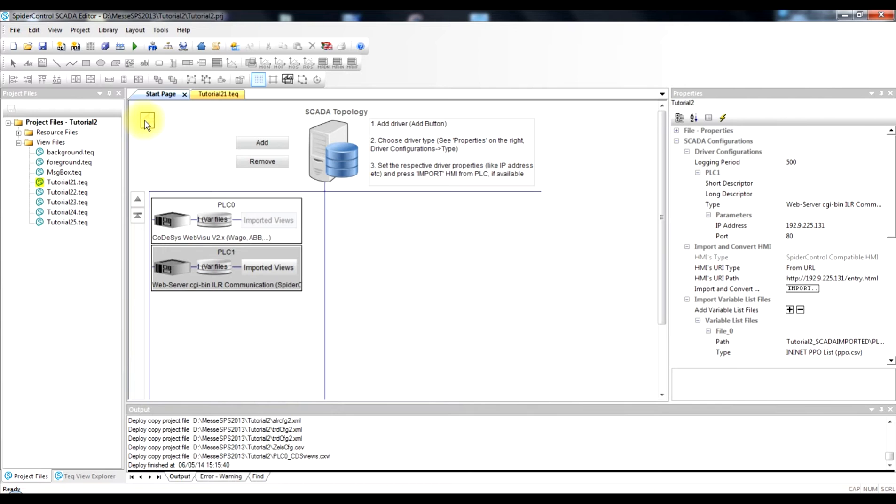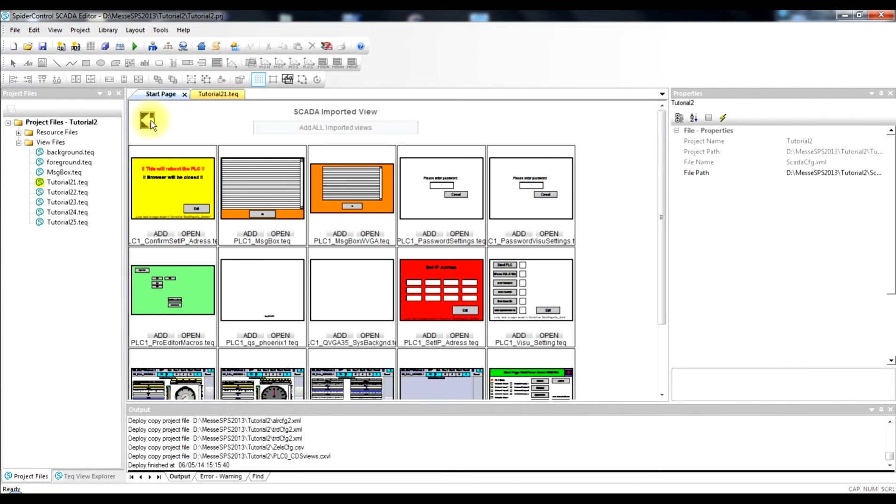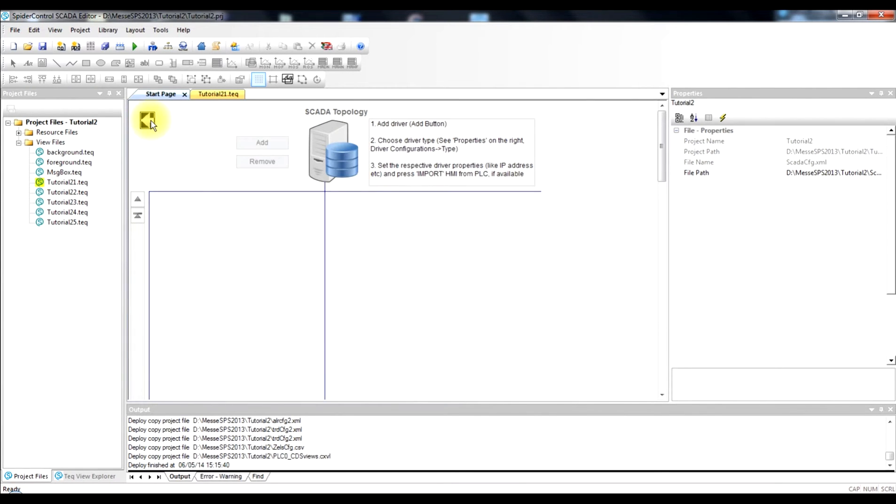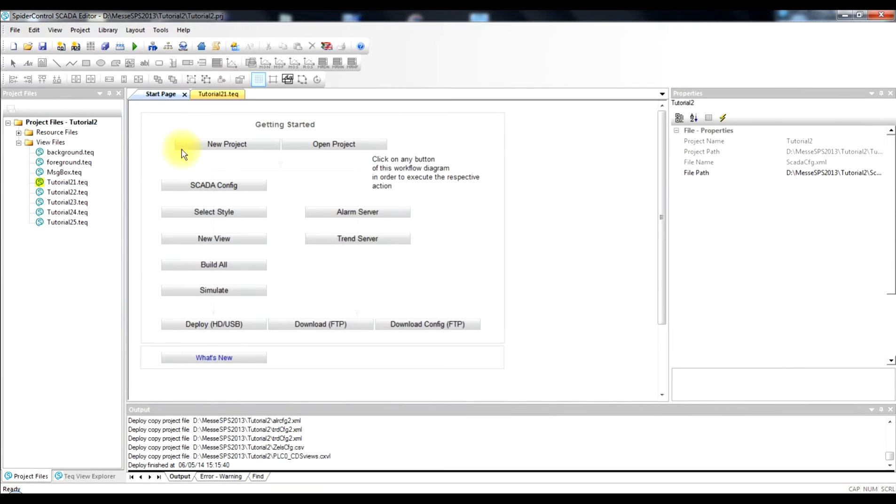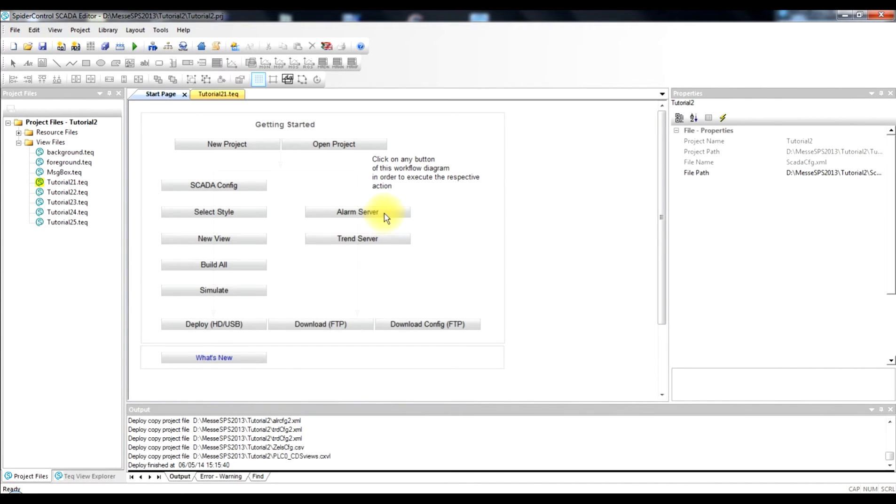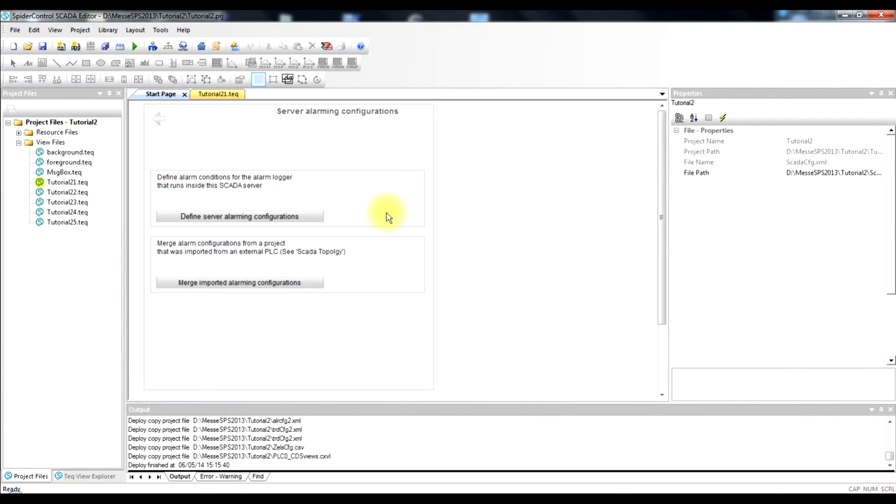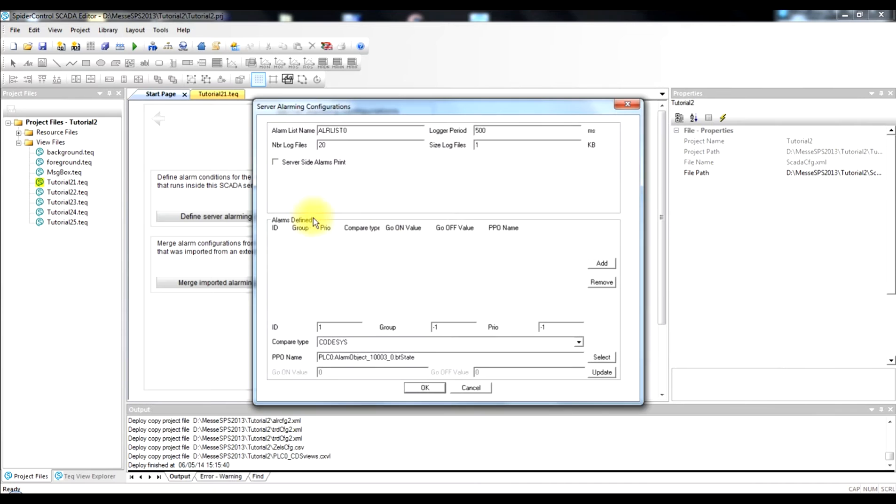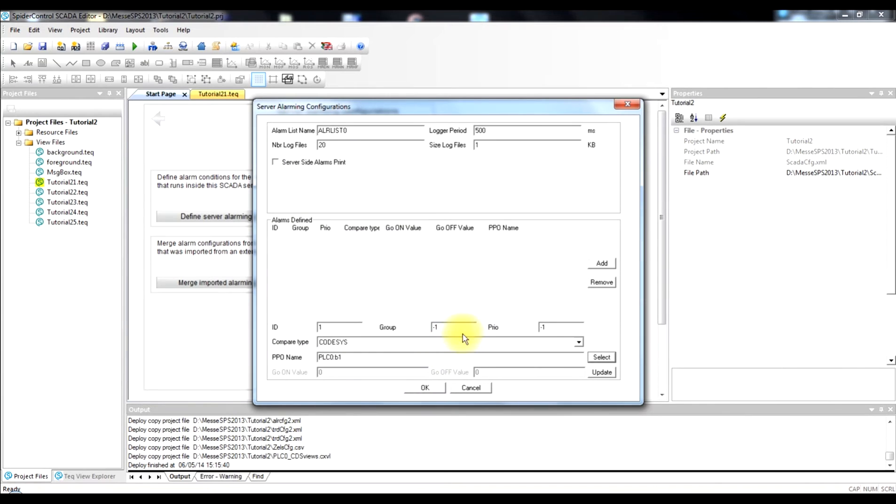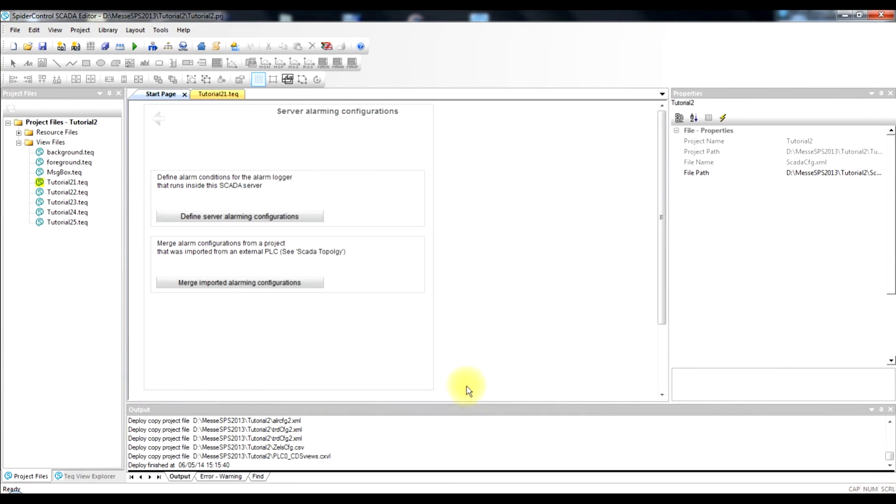So what we are going to do next is have a look at the trend and the alarm configuration. This we can do starting from our overview page from the start page by clicking on alarm trending. The first level that we can enter here is defining alarms manually. So we can select the process points and define a condition for which the alarm would fire. So this is the traditional way how alarm configuration is done.